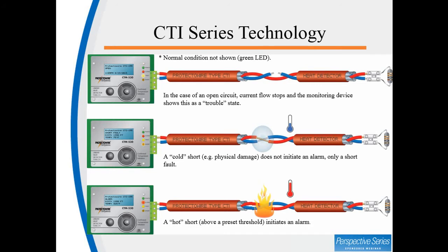CTI Series Technology. We have not shown the normal condition with just the green LED on. The first graphic shows a broken wire or an open condition, which is similar to a regular standard digital. The differentiator for this particular product is the middle and the last graphic. The middle graphic shows a cold short, or something that might be caused by physical damage. The two wires have come into contact, but the module does not see that as an alarm condition. It only sees it as a short fault because there isn't enough heat present. In the last graphic, we show actual heat being impinged on the detector. The two wires are touching, the polymer is melted, and the control module sees that as an alarm condition.